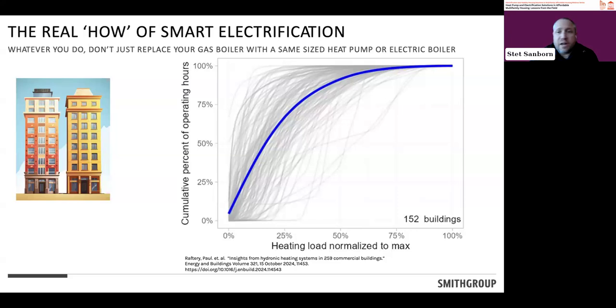And we're seeing this true across the country, not just on the West Coast, but also in the East Coast, because gas boilers were really inexpensive. It didn't cost you much to oversize them. Engineers hate it when you call us afterwards and say we did something wrong. So people add safety factors on safety factors and safety factors. And then all of a sudden you end up with a system that's likely two to three times bigger than it needs to be. And this is actually the case in measured buildings as well.